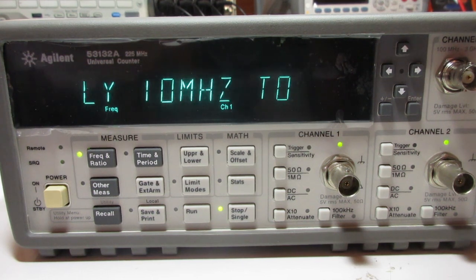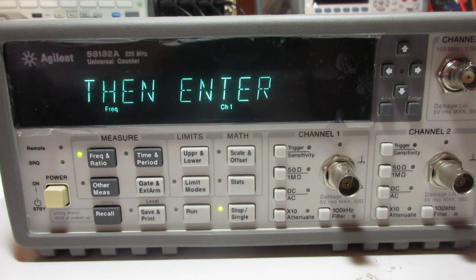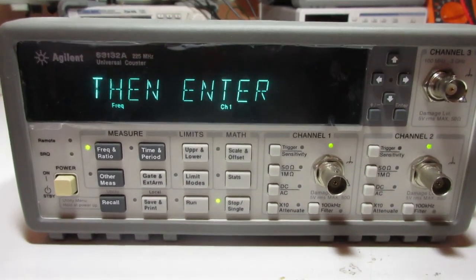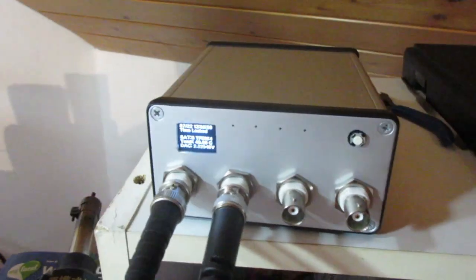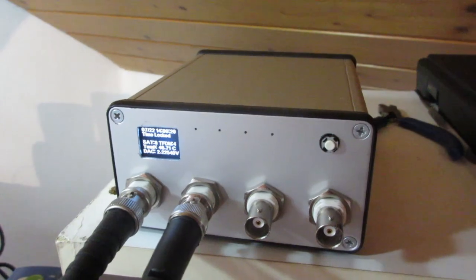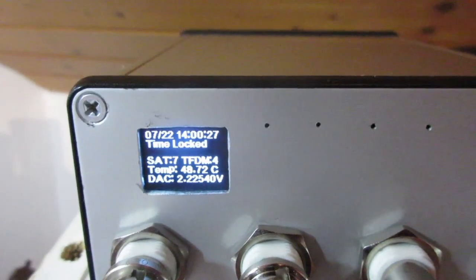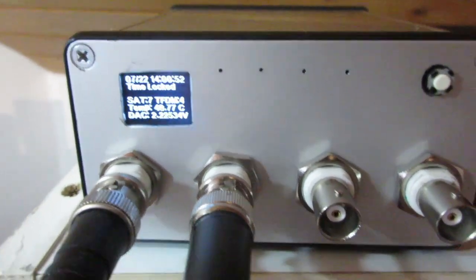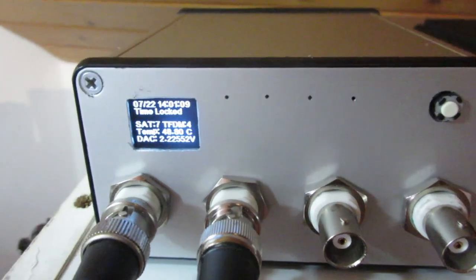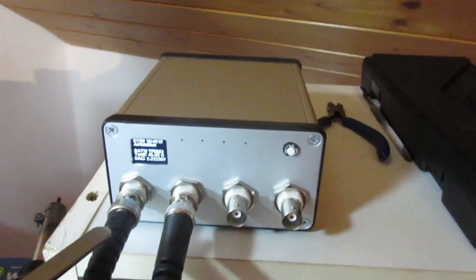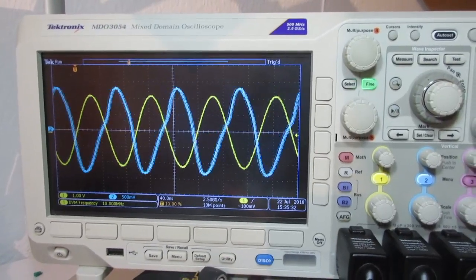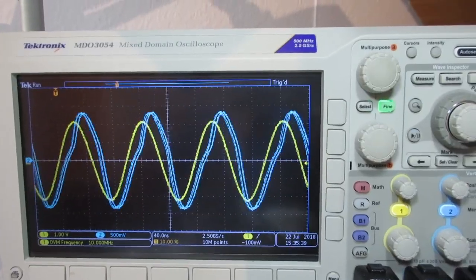The instrument is now asking us to supply a 10 MHz reference signal into channel 1. We will calibrate our time base against a true-position GPS disciplined oscillator with a distribution board providing 4 isolated outputs — a link to that project is in the video description. The GPS shows time locked, 7 satellites, and TFOM of 4; the sky is not very clear right now so satellite count is low. Channel 1 goes directly into the frequency counter, channel 2 is connected to my oscilloscope, and the 10 MHz output from the back of the unit is also on the oscilloscope.